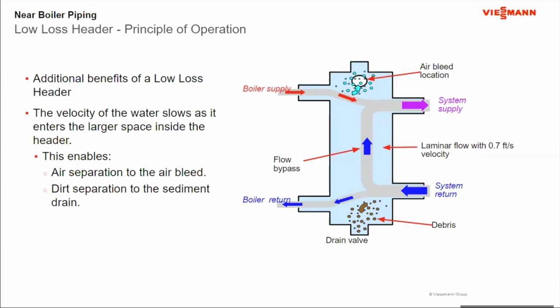Now, a couple of things. We talked about some other features that this does pick up. Okay, coming in here, typically your flow rate is probably going to be in the neighborhood of about 4 feet per second, could be even higher. At that speed, if there's any air that comes out of solution in the boiler, it's going to be entrained along. So when I get to that low loss header, all of a sudden I drop the velocity down considerably. When that velocity drops, I lose the ability to entrain the majority of the air, and it does release in here and tends to catch in the top. So it can be an effective air separator. Okay. Same thing happens on the return side.